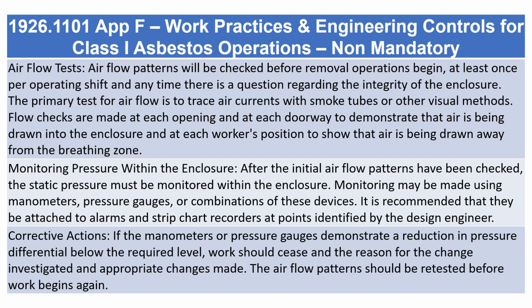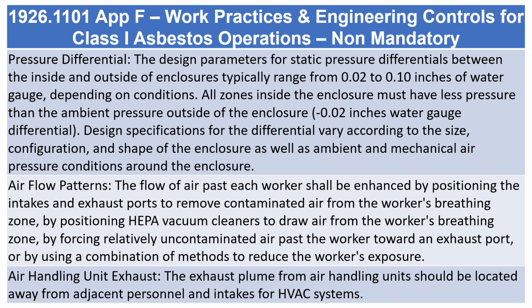Corrective actions. If the manometers or pressure gauges demonstrate a reduction in pressure differential below the required level, work should cease and the reason for the change investigated and appropriate changes made. The airflow patterns should be retested before work begins again. Pressure differential. The design parameters for static pressure differentials between the inside and outside of enclosures typically range from 0.02 to 0.10 inches of water gauge, depending on conditions.